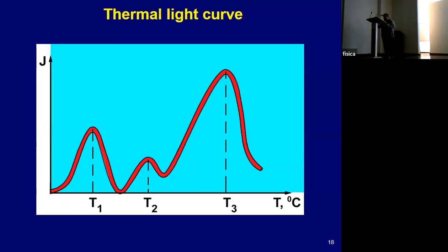In this case, one of two parameters of the thermoluminescence curve is determined: the total light sum released during the heating process, according to the integral method, or the maximum peak height, and the corresponding method is called the peak method. The integral method is more widely used. It is more accurate and less dependent on the technical parameters of the measuring installation, like heating rate, final temperature, etc.